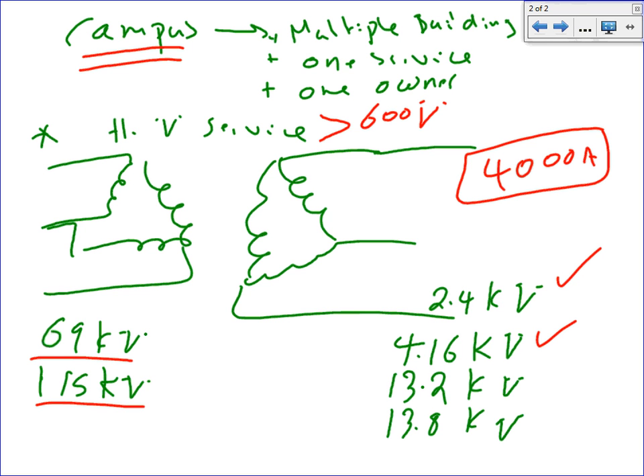4160, the common term for it, 4160 volt or 4.16 kV, 13.2 or 13.8. This, when I was doing medium voltage, was our voltage of choice. So if my plant, and a lot of people, guys, are using it right now, because of future expansion, needs a primary service higher than 600 volt, take 13.8. 13.8 is the best, more efficient, higher voltage primary service.